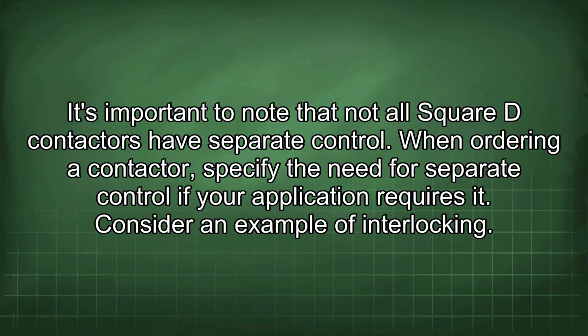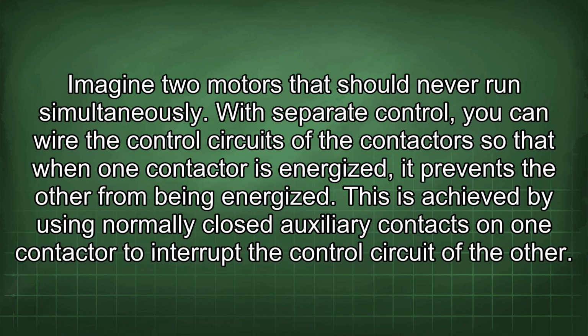Consider an example of interlocking. Imagine two motors that should never run simultaneously. With separate control, you can wire the control circuits of the contactors so that when one contactor is energized, it prevents the other from being energized. This is achieved by using normally closed auxiliary contacts on one contactor to interrupt the control circuit of the other.